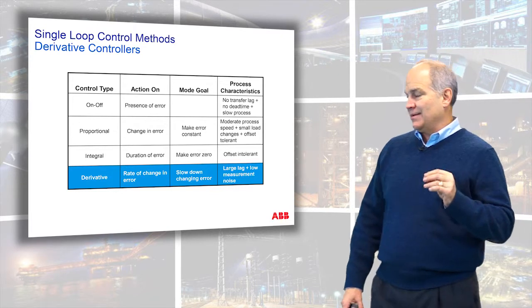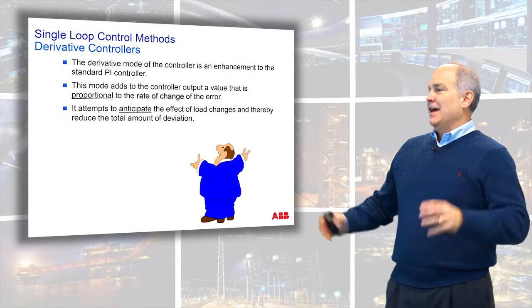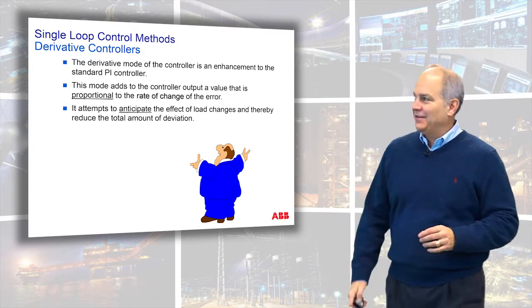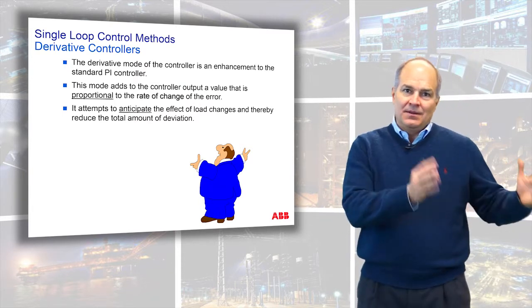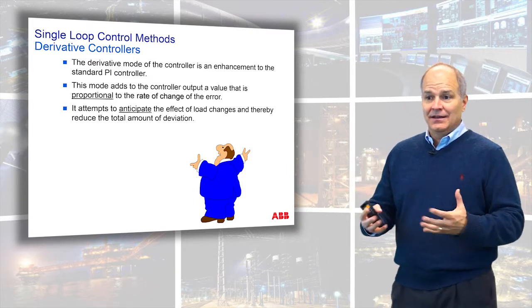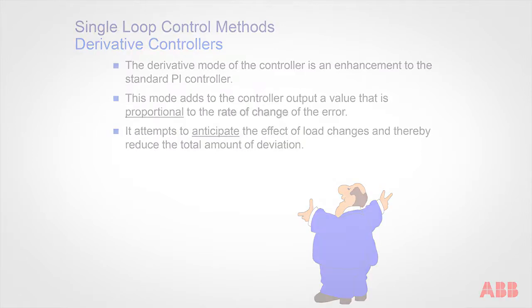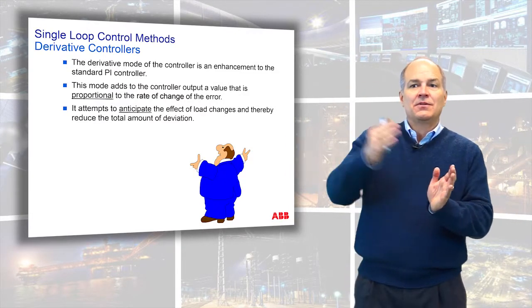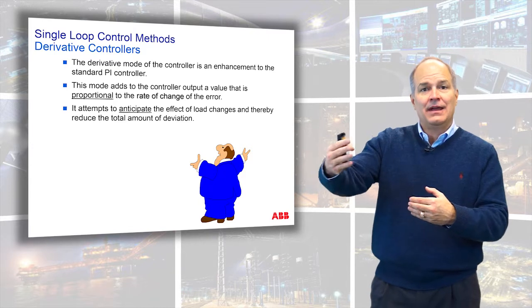Derivative deals with the rate of change of the error, and its job is to slow down a changing error. The derivative mode is an enhancement to the standard PI controller — you won't typically find derivative by itself, it usually comes with PI. This mode adds to the controller output a value proportional to the rate of change of the error. Based on the current slope, it anticipates where the error is going to go and makes a correction now, so the process doesn't go there.